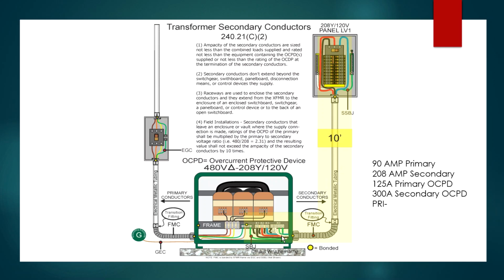Now, incidentally, we are not going to be sizing the grounded conductor today. We're saving that for the same video when I talk about how to calculate the supply side bonding jumpers, the grounding electrode conductors, and all of that. We're going to save the sizing of that, so that's going to be another series. So you have to watch that once we get to that. We're not going to size the supply side bonding jumper in this one today. We're just dealing with these conductors in the secondary conductor rule today.